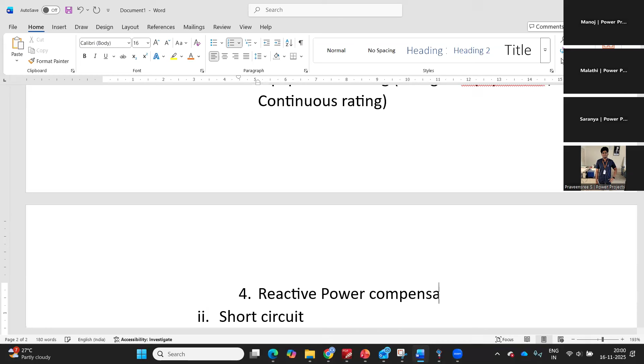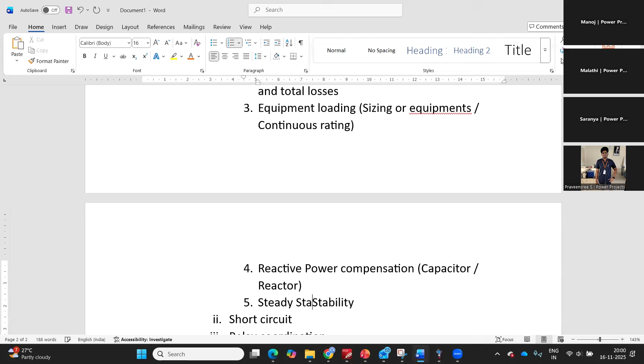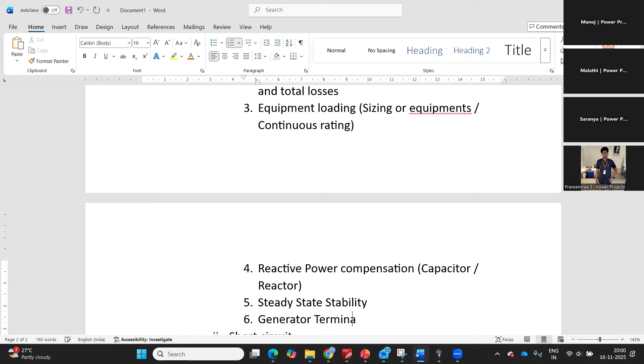What is the capacitor bank which is needed, what is the reactor which is needed, or probably to find out the steady state stability limit, steady state stability, or to set the generator terminal voltage, to check whether OLTC is required or not. If required, what's the OLTC range and the step.